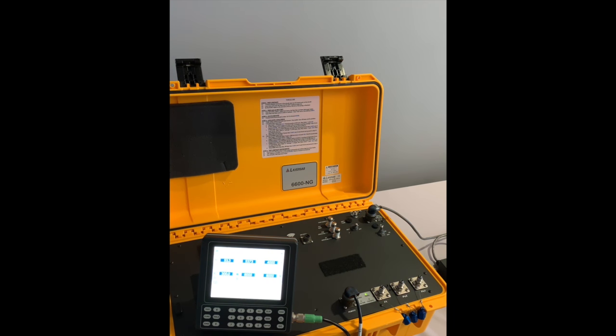You have to imagine that you hooked up your test set to the aircraft, but there is a very large leak going on, like you forgot to connect the static adapter or Pitot adapter, or none of the fittings on the hose assembly have been tightened properly. For the purpose of the training and the simulation, I left the ports open, but for you, it would be a situation like I just described. What we're going to do now is go into control and see what happens on the test set when it is going under control.